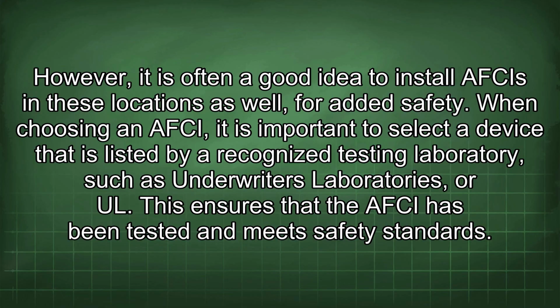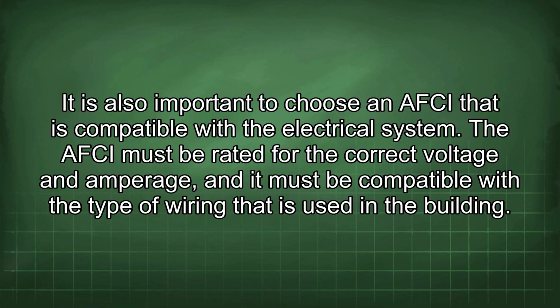When choosing an AFCI, it is important to select a device that is listed by a recognized testing laboratory, such as Underwriters Laboratories or UL. This ensures that the AFCI has been tested and meets safety standards. It is also important to choose an AFCI that is compatible with the electrical system. The AFCI must be rated for the correct voltage and amperage, and it must be compatible with the type of wiring that is used in the building.